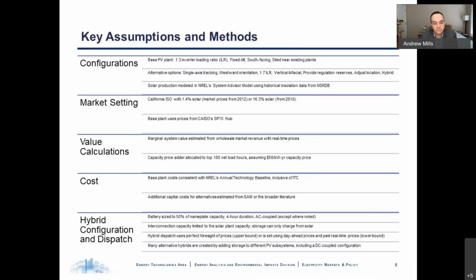All of our cost estimates will be reduced by the federal investment tax credit mentioned earlier, both for solar and for storage. When we calculate the impact of adding storage, we always size the battery to 50% of the nameplate capacity, and then use a 4-hour duration storage that's AC coupled, except where noted. We also assume that the interconnection size is always based on the solar nameplate capacity, and that the storage can only charge from solar.